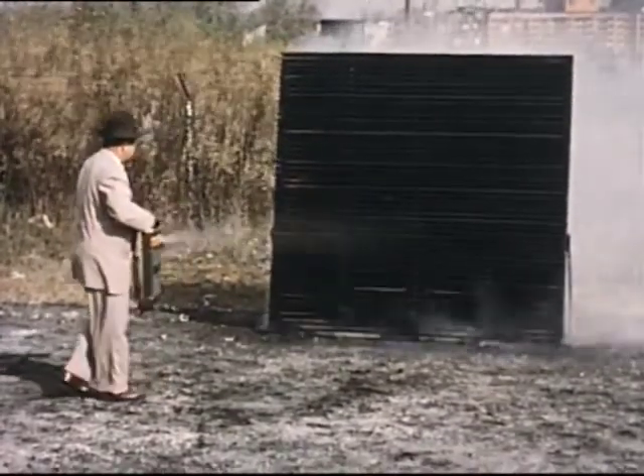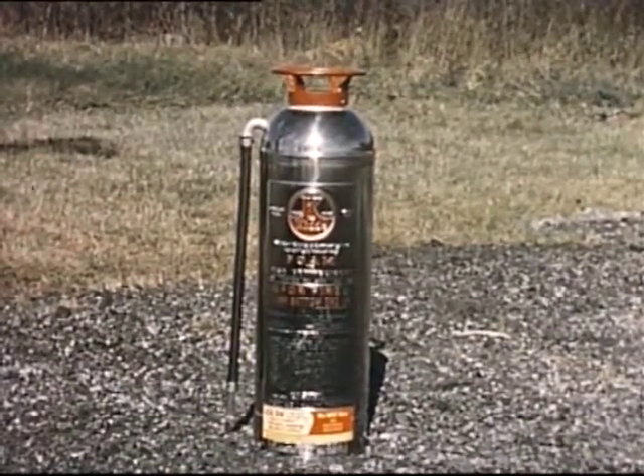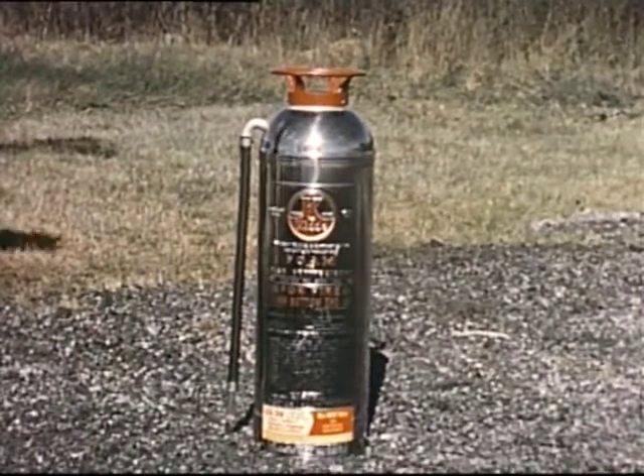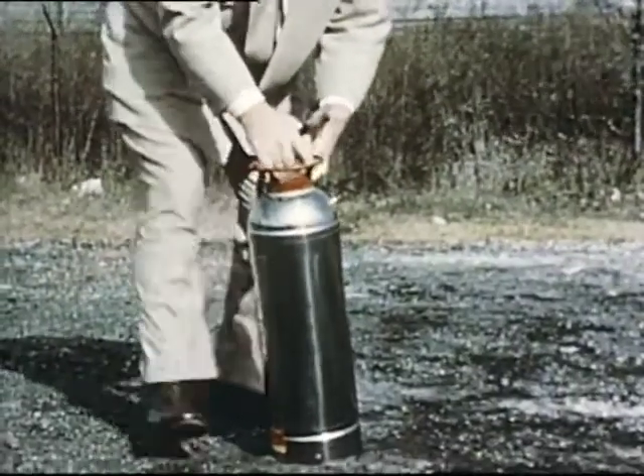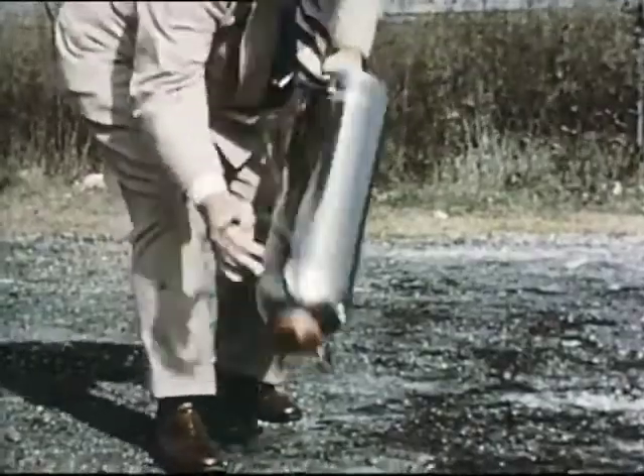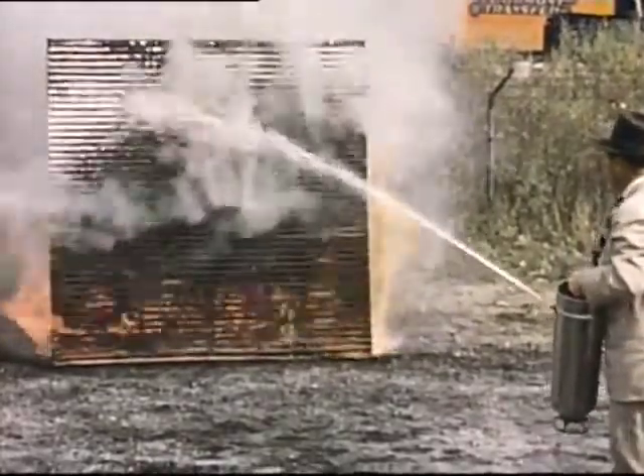Use all of the water and be sure. No one extinguishing agent is best for all types of fires. Foam also is excellent for a Class A fire because it has both smothering and wetting action. The foam extinguisher is inverted just like the water extinguisher. When turned upside down, the foam solutions mix to form a gas which forces the foam out of the container. To fight a Class A fire, you use foam just the way you use water. A soda acid extinguisher can be used the same way too. All three — water, foam, and soda acid — come in similar containers and are applied in the same way on Class A fires.